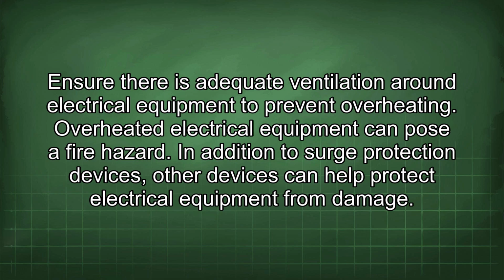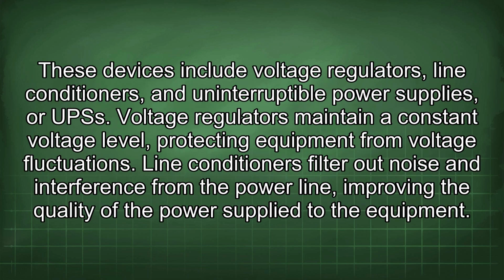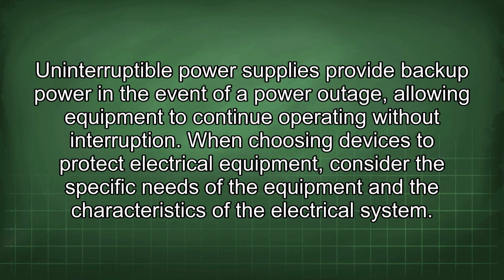In addition to surge protection devices, other devices can help protect electrical equipment from damage. These devices include voltage regulators, line conditioners, and uninterruptible power supplies, or UPSs. Voltage regulators maintain a constant voltage level, protecting equipment from voltage fluctuations. Line conditioners filter out noise and interference from the power line, improving the quality of the power supplied to the equipment. Uninterruptible power supplies provide backup power in the event of a power outage, allowing equipment to continue operating without interruption.